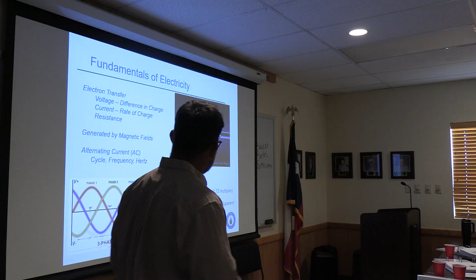That generator has to be internally wound, doesn't it? Internally wound? Yes. I've not seen one that's externally wound, so I'd say yeah. Okay. I know if you got a 50 horse motor or a 50 horse pump, it takes twice the kW to start if it's not internally wound. We'll talk about that, because that inrush current is a big, big, big piece of this. Yeah, so most of these would be inverter duty, which is what you're referring to. Yep, great point. And I would say not just the generators, but oftentimes the stuff downstream are going to need to be of that type of construction as well.